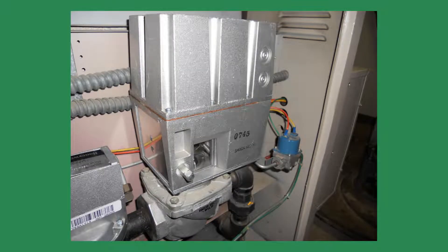The actuator should be replaced by someone familiar with boilers. When ordering a replacement Honeywell gas valve actuator, be sure to get all the numbers on the actuator. The four-digit number is a date code that tells you when the actuator was manufactured. The actuator model number consists of a letter followed by four numbers and then another letter, with usually four numbers after that — these are crucial to finding the correct unit. In this case, the actuator is a V4062A1009, and with that number the wholesale house should be able to get the proper replacement.